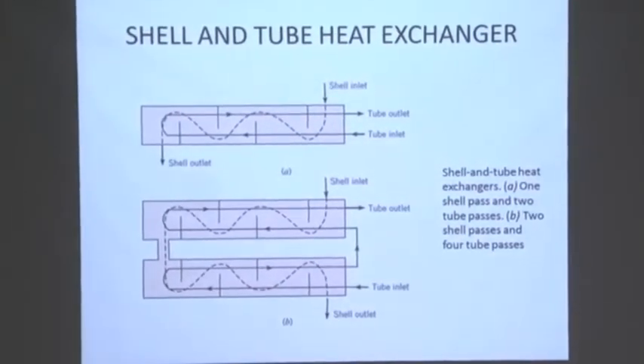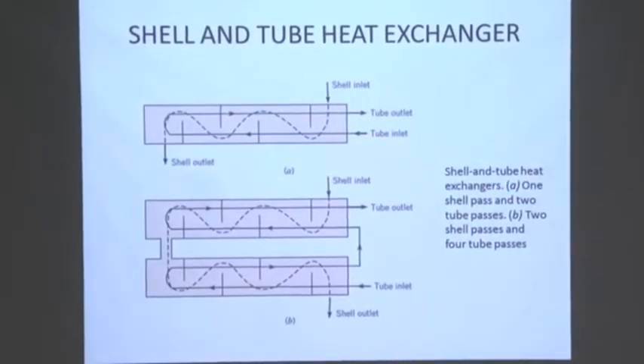Number one is one shell pass and two tube pass. You see, two tube pass means the tube inlet goes in one direction, then comes back out - it's a U-tube type, tube outlet. That means in a U shape, it comes here - this is one pass and it comes back like that, so inlet and outlet are on the same side.